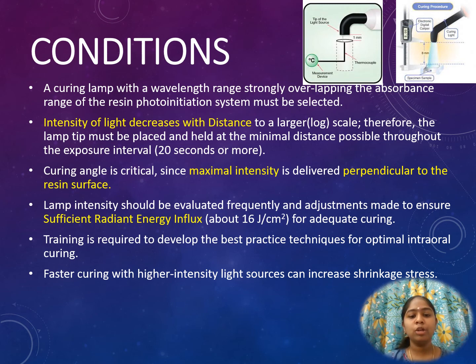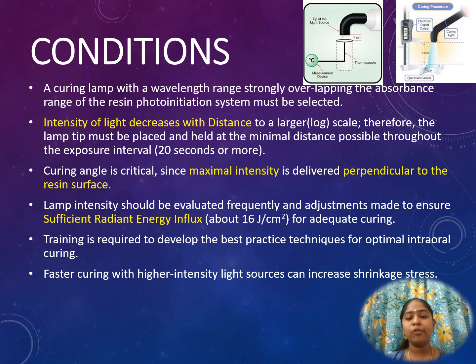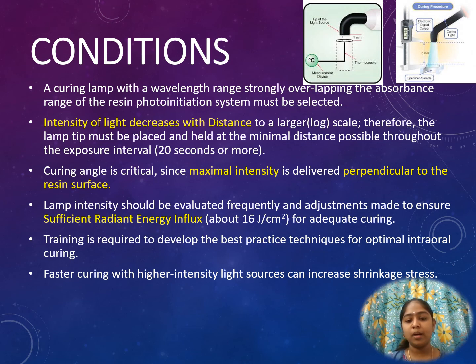Lamp intensity should be evaluated frequently, and adjustments should be made to ensure sufficient radiant energy influx — about 16 joules per centimeter squared for adequate curing. For example, if a lamp emits 1000 joules per centimeter squared but due to energy dissipation as heat or removal of unnecessary wavelengths only 750 joules per centimeter squared is delivered, and the material requires 800 joules per centimeter squared, there will be a shortage of energy. Training is required to develop the best practice techniques for optimal intraoral curing.